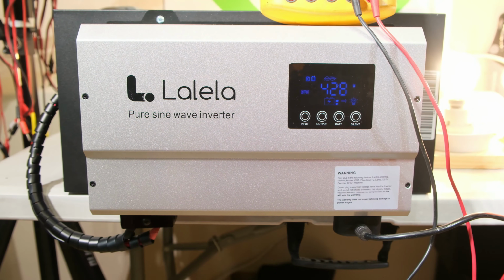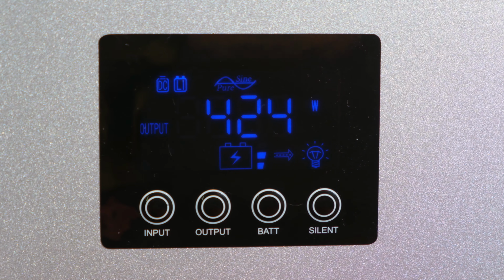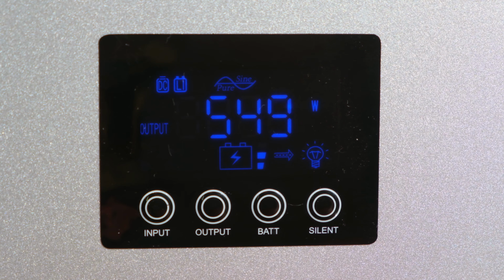Now the specifications of the unit says it can handle 600 watts. I'm now going to increase the power output and see if I can get to 600 watts. Right, so that's 424 watts. I'm going to increase it some more. I've now added an additional 50 watts, so I'm now at 478. The fan has increased in its velocity. I'm now going to increase the output on my load. There I've now exceeded 500 watts. The unit is stable. Okay, I'm at about 550 watts. The alarm is making a sound more often now.